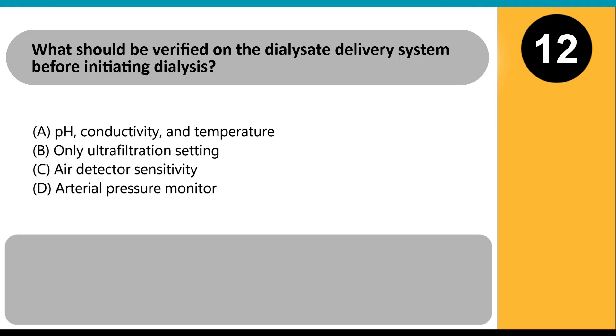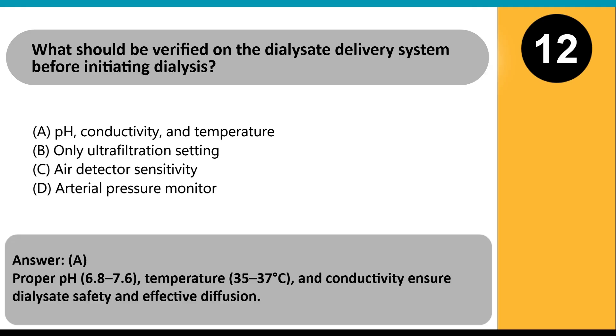What should be verified on the dialysate delivery system before initiating dialysis? A. pH, conductivity, and temperature. B. Only ultrafiltration setting. C. Air detector sensitivity. D. Arterial pressure monitor. Answer A. Proper pH (6.8 to 7.6), temperature (35 to 37 degrees Celsius), and conductivity ensure dialysate safety and effective diffusion.